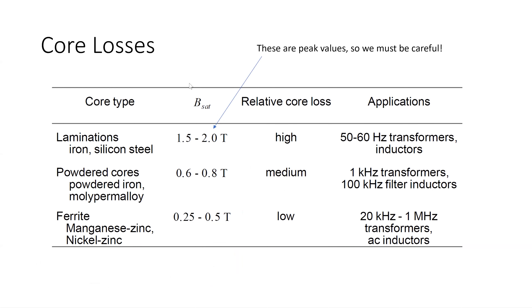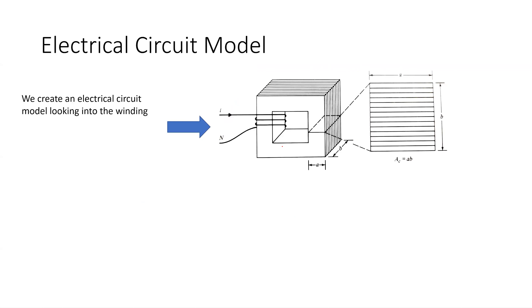Inside these things we have hysteresis loss and eddy current losses. Different materials have different saturation levels — different peak B fields they can carry. Ferrite has a max B field of about a quarter to half a Tesla. For iron at 60 Hz, it's somewhere around 1.5 to 2 Tesla. For a graph of 29-gauge M19 steel at 60 Hz, for a given B field this value tells me a power density — for example, at 1.5 Tesla, the loss in that core would be about two watts per pound.